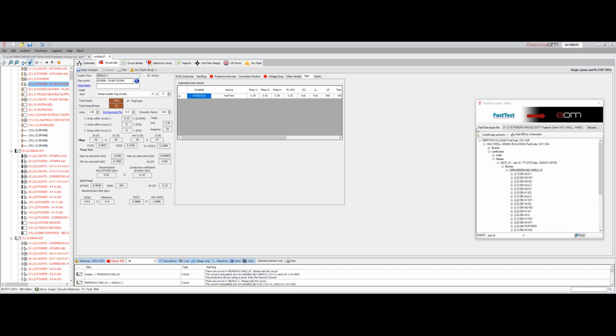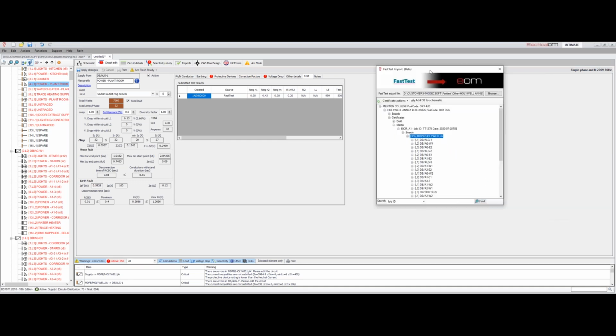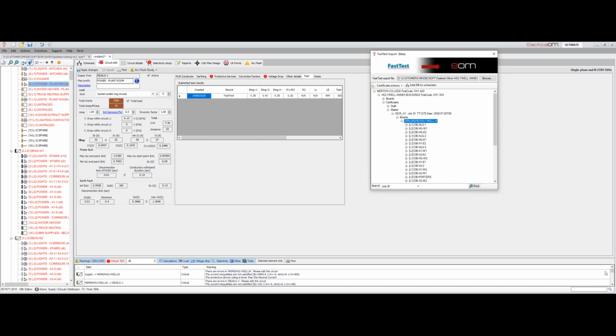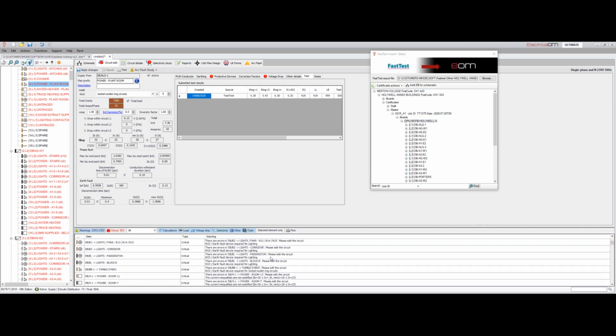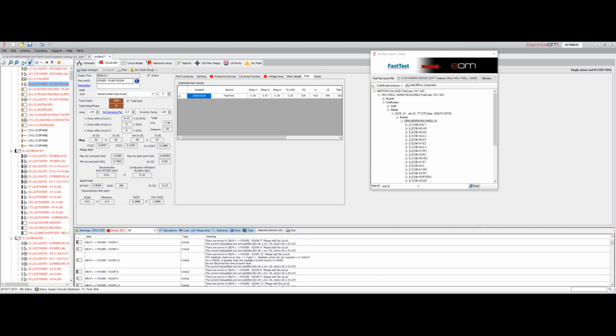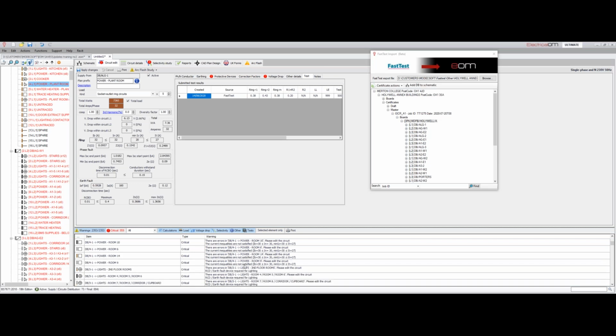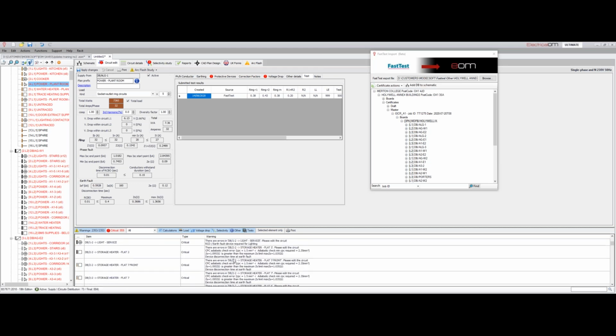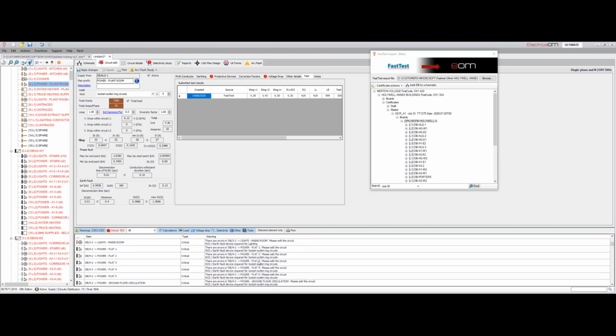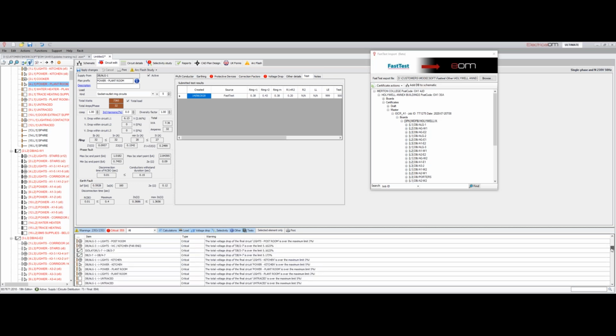One of the great things about the software is we can go a few steps further. If I scroll down to our warning system, we can see any errors where we've got issues between the device ratings and the cable sizes. There are quite a few issues here around coordination of devices and cable sizes, plus various issues to do with disconnection times based on the manufacturer and type of device selected. Going further down, we can even see volt drop issues, which are now clear on the system.